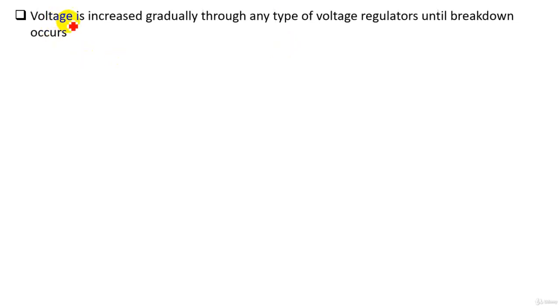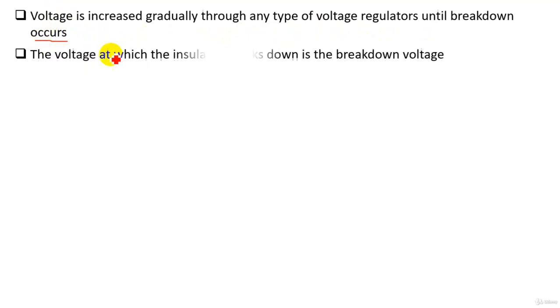Now let's see the operation of the high voltage testing transformer in our lab to test the insulator. First, voltage is increased gradually through any type of voltage regulators until breakdown occurs. When breakdown occurs, the voltage at which the insulator breaks down is the breakdown voltage, and this voltage can be measured by using any high voltage techniques for high voltage measurement.